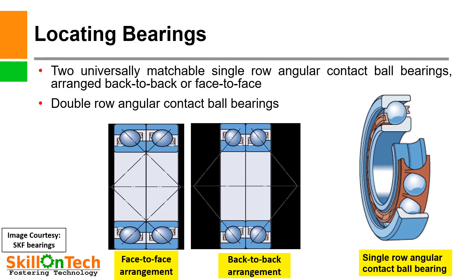Continuing with locating bearing types: two universally matchable single-row angular contact ball bearings arranged back to back or face to face are also suitable. In this picture you can see a face-to-face arrangement and a back-to-back arrangement of angular contact ball bearings. Here you can also see single-row and double-row angular contact ball bearings, all of which are suitable for locating bearings.